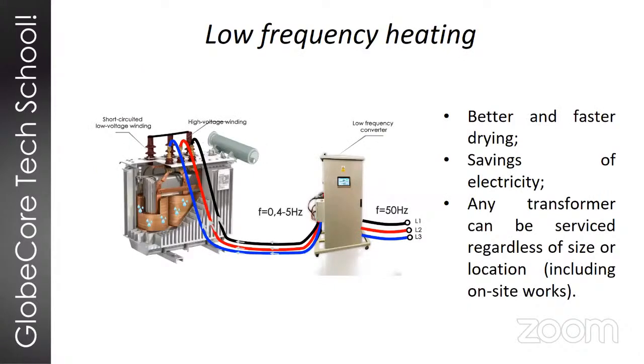So low frequency heating is a very promising approach to drying of transformer solid insulation. First, it was used in the mid-1980s when drying distribution transformers. The idea is to apply a low frequency current, with a frequency of maybe 0.4 to 2 hertz, a low voltage current, to the high voltage windings, and to short the low voltage windings as well. During this process, the high voltage and low voltage windings of the transformer are evenly heated to a typical temperature of 110 to 120 Celsius.